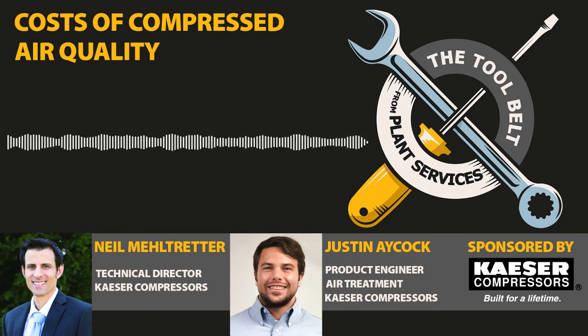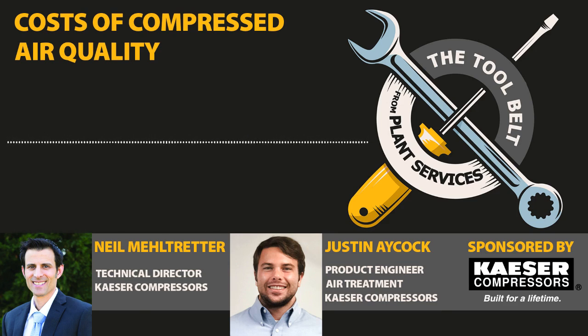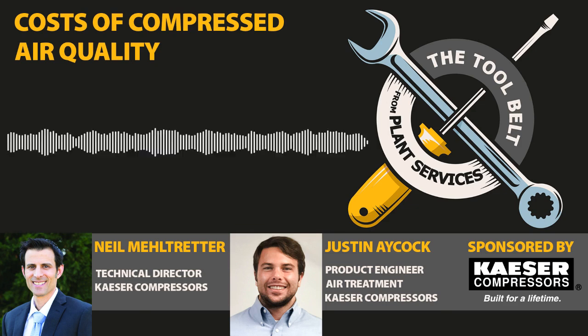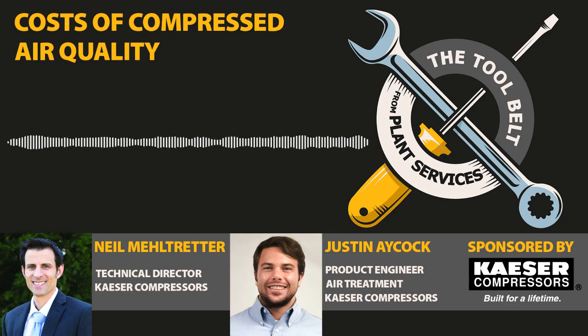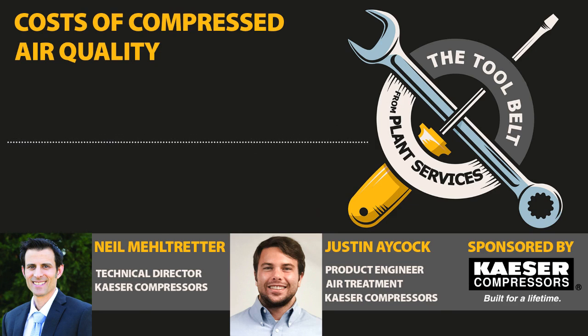So those are things obviously we would like to avoid. So that's what we say. And when you design the system, you're looking at 15 feet per second in the compressor room, 30 feet per second in the distribution piping, and 45 feet per second at the point of use. And that can really help ensure that you have the air quality that you started with, right? Because we're designing the system, we're making sure that everything works, but that piping aspect is really important.